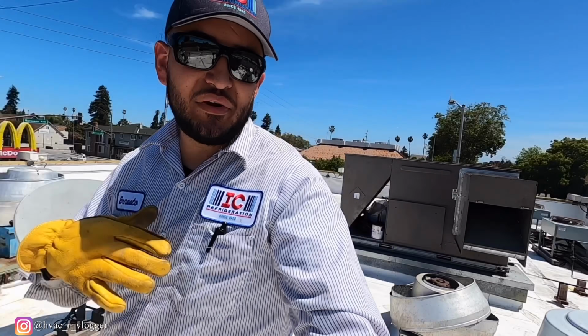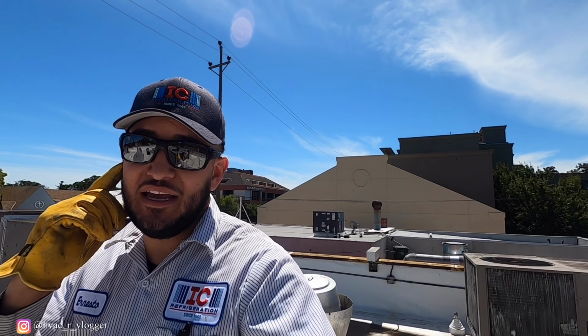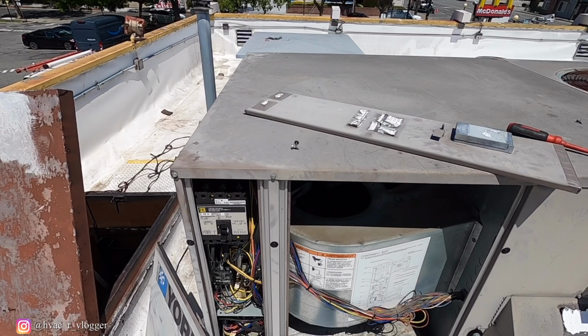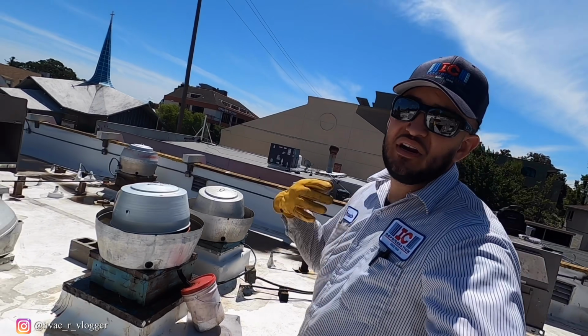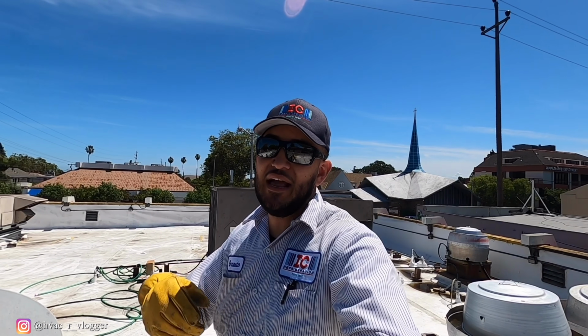So this is something that Chris from HVACR videos always talks about, is always try to hear your surroundings. And that's when having headphones and things like that kind of affects you, especially if you're newer to the trade. I was able to tell that this unit hasn't been running just by hearing it, you know what I mean? I wasn't hearing anything whatsoever. So I just came here, opened up the panel, found a trip. I'm like, okay, I'm gonna check that unit out. So imagine if I would have left, that we would have been called out again for another unit in the same store when I could have just taken care of it.